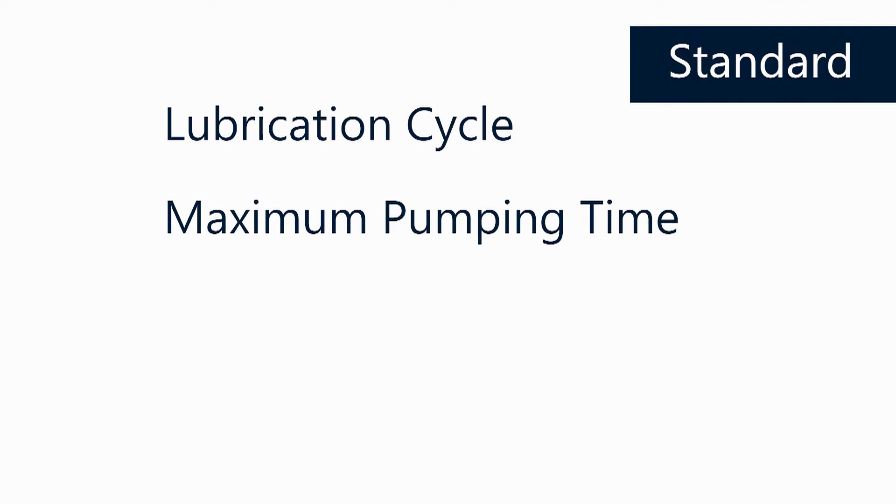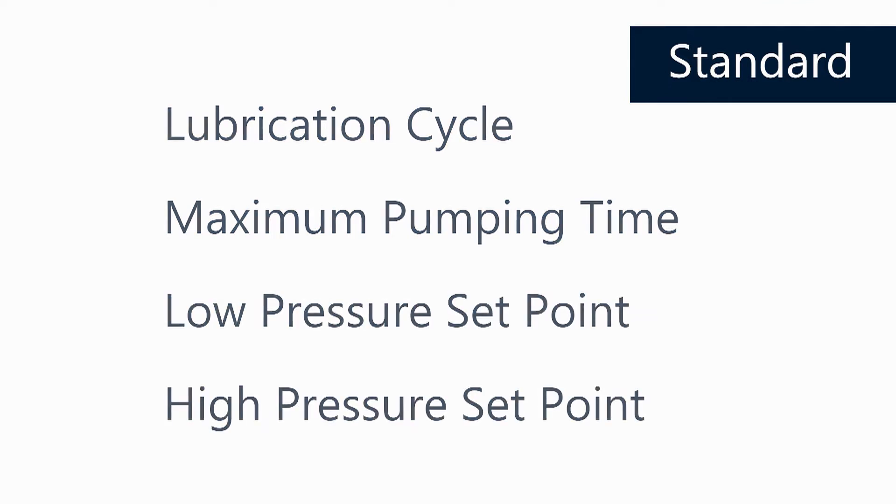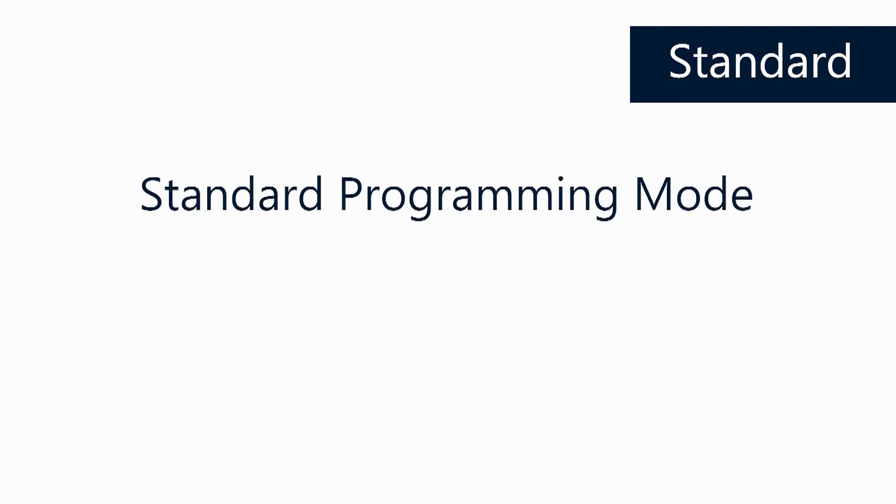The second type of parameters are the ones we are more familiar with: standard parameters. The standard parameters include set points for the lubrication cycle, maximum pumping time, low pressure set point, and high pressure set point. To adjust standard parameters, use the password 103.